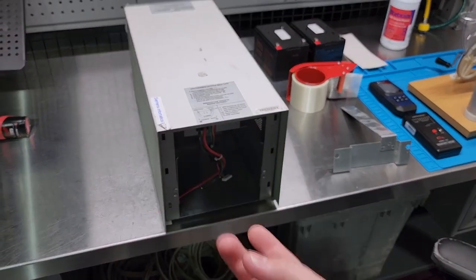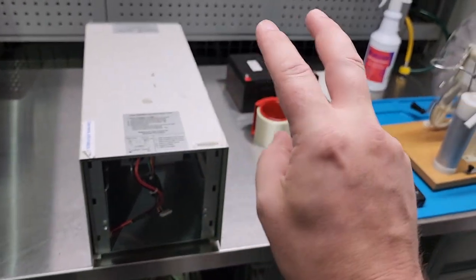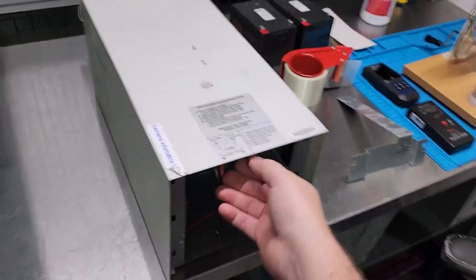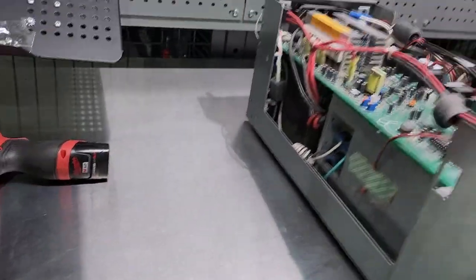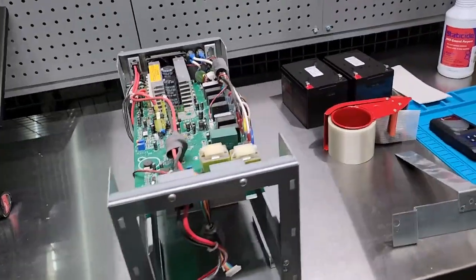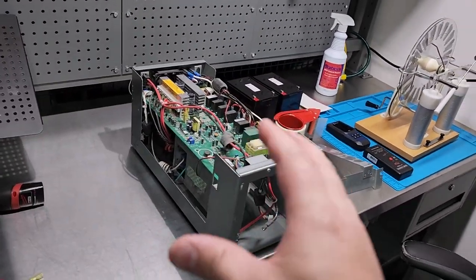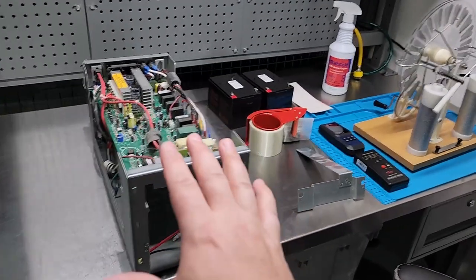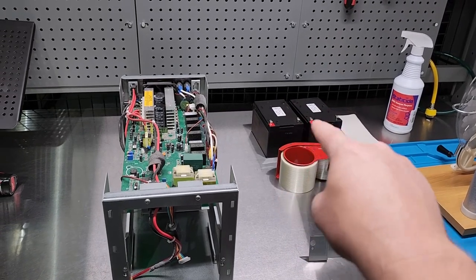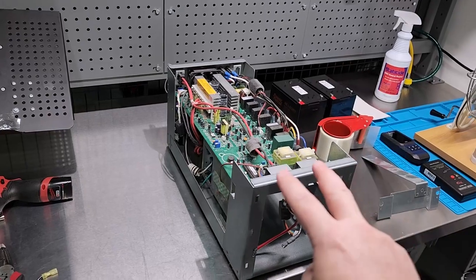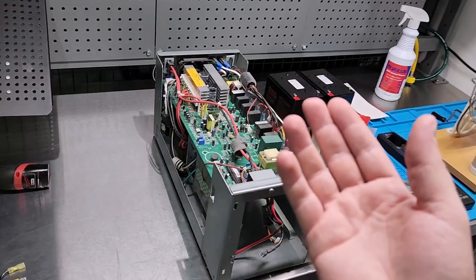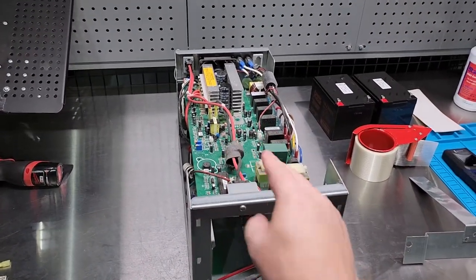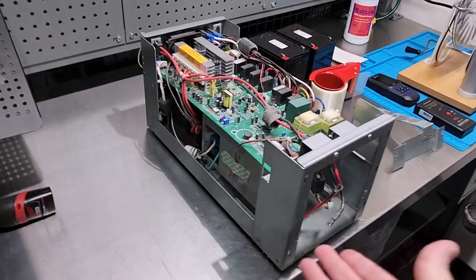So, you can see I've got the new batteries in, ready to get put back in. But there's a little bit of prep we've got to do to some of the connectors. Before I put the batteries in, I want to check and make sure that the internals on my UPS are safe. This is a 1200 or 1500 VA UPS system. The VA is actually the rating for the capacity of the UPS system. This is a standard 120 volt unit. It takes two 12 volt batteries wired in series. So, you have a 24 volt configuration, and it steps up 24 volts and then chops it up and creates the sine wave when it's being told to do so.